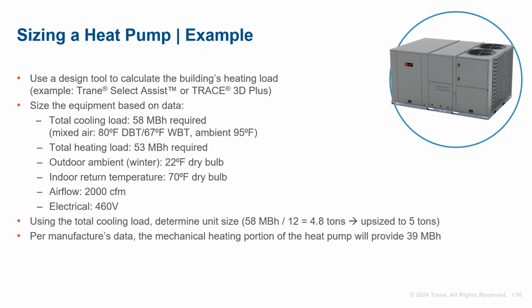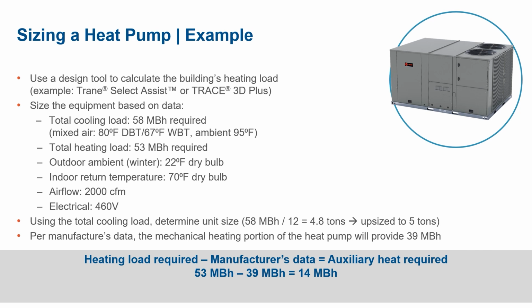Using this as our baseline, we can use either the manufacturer's catalog data or a performance program such as Trane Select Assist to determine the unit's heating mode output. With an outdoor winter design condition of 22 degrees Fahrenheit and return air temperature from the space of 70 degrees Fahrenheit, the manufacturer's data shows that the unit in heating mode will provide about 39 MBH. And because 39 is less than the building's required heating capacity at winter design conditions of 53 MBH, an auxiliary heater must be selected to supply the remaining 14 MBH of heat required.